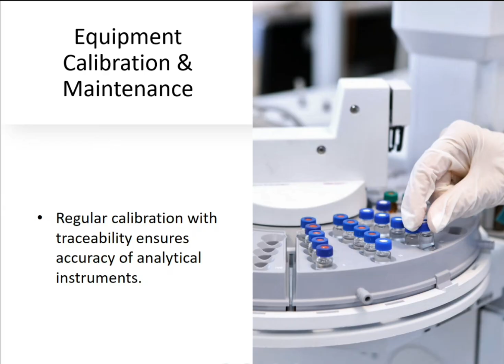So when we talk of calibration of pipettes, basically why is it important? It's important because most of our QC material or samples, we need to dilute or add some liquid. If your pipette is not calibrated properly and you are reconstituting your QC material, you are thinking that you are reconstituting with an X amount of volume, maybe say 2 ml, 3 ml, 5 ml, whatever. But if it is not calibrated, instead of 5 ml, it may be inaccurate. You would be reconstituting with say 4.5 ml instead of 5 ml. So if you do that, it is expected that your QC values are not going to be in range. So you're going to be struggling with your QCs because your pipette is not calibrated. So there is importance not only of the analytical instruments, even the non-analytical instruments need to be calibrated regularly, right?